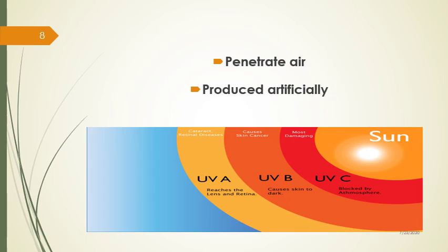It does penetrate the air, effectively reducing the number of airborne microorganisms and killing them on surfaces, in operating rooms, and rooms that contain caged animals. Ultraviolet lights lose effectiveness over time and should be monitored often to help sanitize the air without irradiating humans.